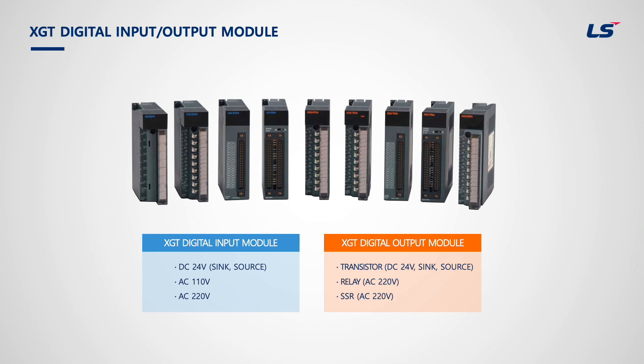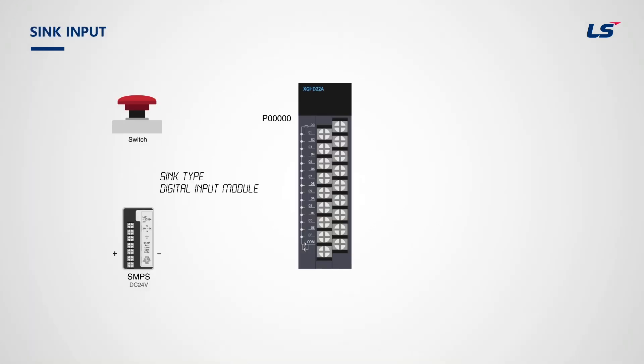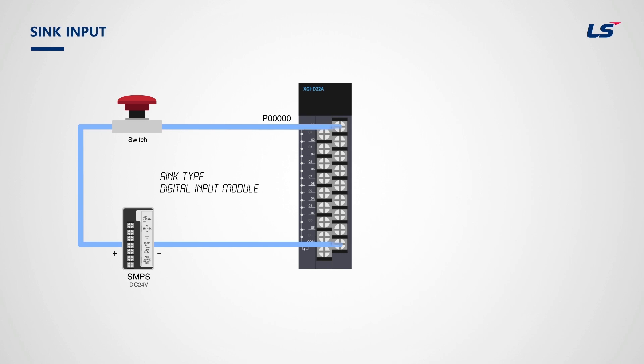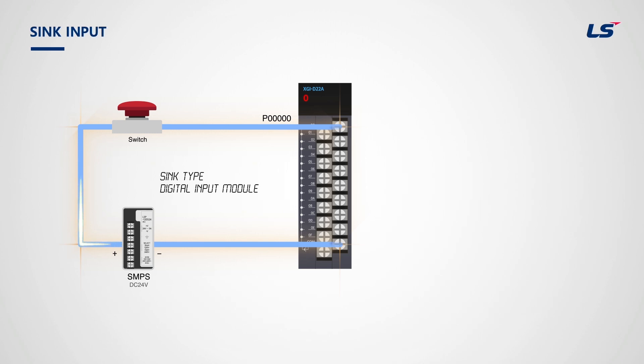Let's take a look at digital input. This is a sink type digital input module. For the sink type input module, the COM terminal — which is the common terminal for the PLC input module — is connected to DC 0 volts power source. The current flows from positive to negative, so the current flows into the PLC when the switch connected to the PLC input is turned ON. When you push the switch, the current flows into P0 and the number 0 bit becomes ON. Remember that the zero voltage of the SMPS is connected to COM.